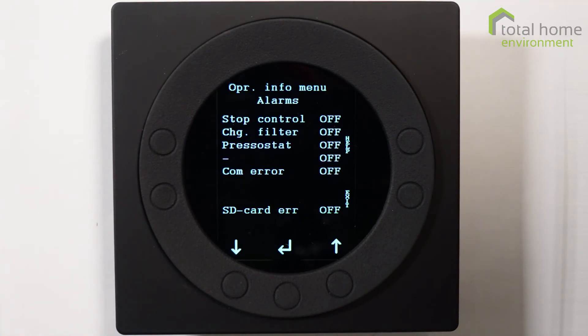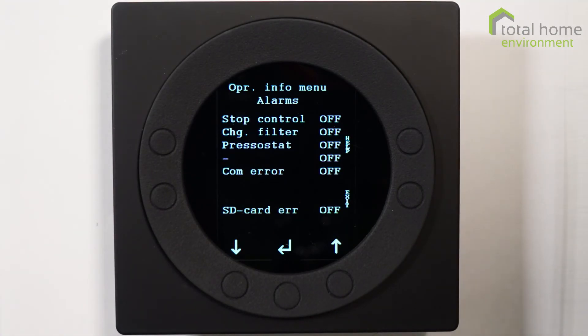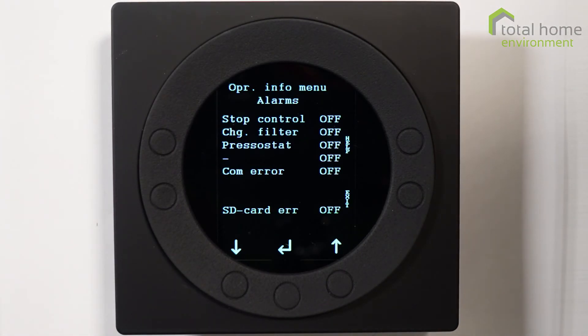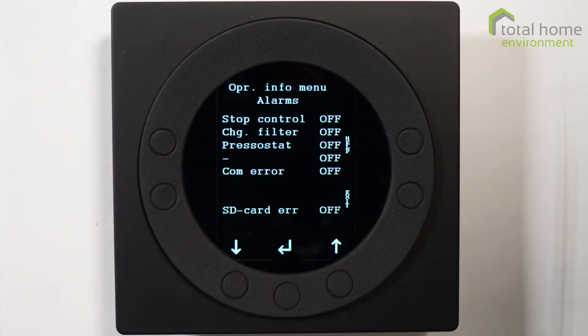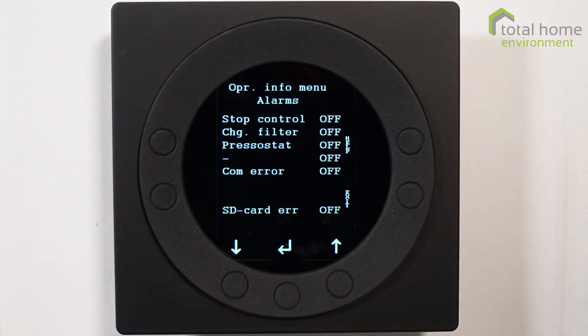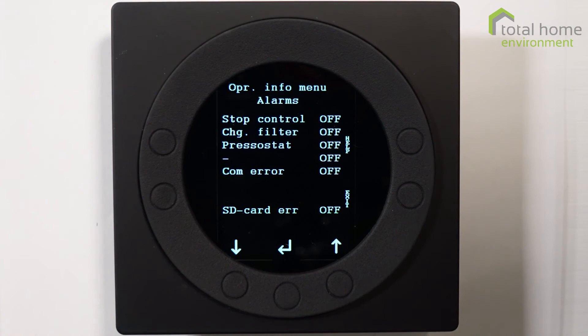Pressostat is a fancy name for a mechanical pressure switch, which is connected to the refrigeration circuit on the system. If the pressure within that circuit exceeds certain parameters - in the case of the Combi it's 18 bar - then that switch will disconnect the compressor. Usually the cause of a Pressostat alarm is someone has forgotten to change filters, or there's a blockage somewhere, or someone's closed off air vents, because unless the machine has decent airflow it can't perform properly.